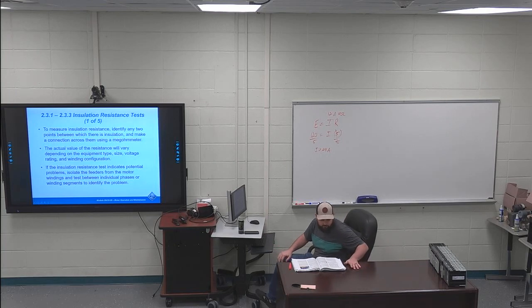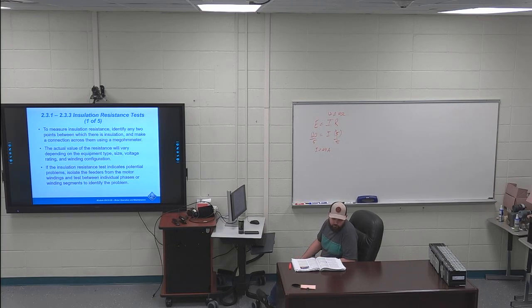So you want at least, the next sentence after that PIR equation is highlighted: the recommended minimum value of polarization index for AC and DC motors and generators is 2. So you want your resistance after 10 minutes to be twice what it is after 1 minute. This is a highlight for a polarization index.